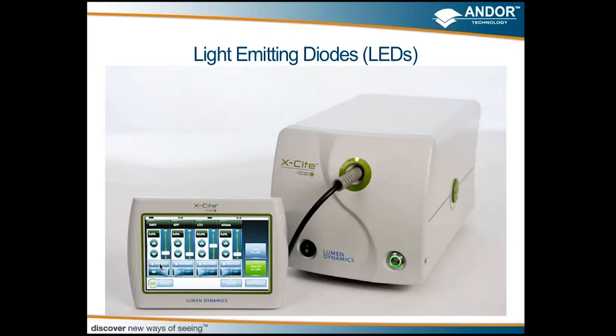The system we're using most often is the Lumen Dynamics XLED, which has four individually controllable LEDs, each controlled via its own TTL. This is a nice system for integration with pClamp because you can control each line as its own light source, and these LEDs turn on and off just like a light switch. Very long shelf life, 20 to 30,000 hours or more, very uniform illumination, and you can see from the image here they couple to the microscope or the Mosaic 3 with the liquid light guide.